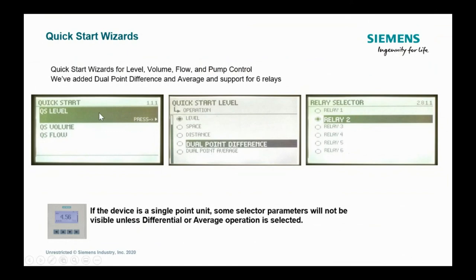It will set you into a number of wizards, quick start level, volume or flow, and basically it'll walk you through in English. So you don't have to use the handheld programmer, and you basically just answer a number of questions, and you don't have to pull out the manual or the Siemens decoder ring to know what is the code number for an XPS-15 transducer to enter into parameter P004. Okay.